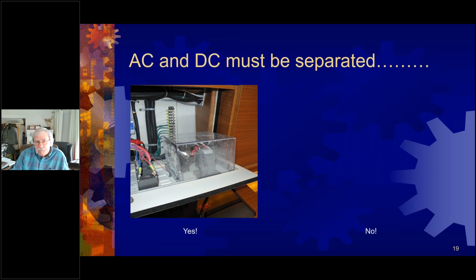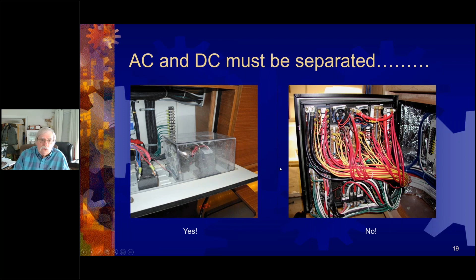What a lot of builders are doing now is they'll have the AC and DC panel boards as two separate panels completely, so that you're mitigating the risk of someone getting shocked if they're in there working on it. And that's really the intent of this. We do have a standard that states that to access live AC you need to use hand tools to gain access to these live connections, and that's one way to comply with the standard. In this case, you would have to unscrew the cover to gain access to those live terminals.